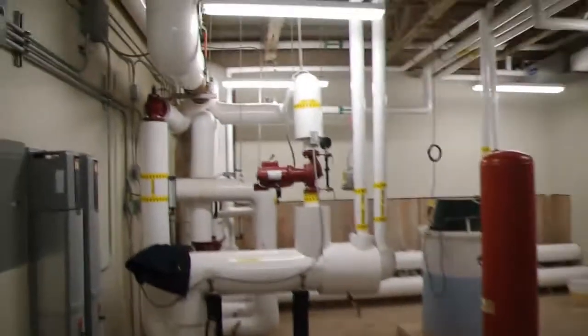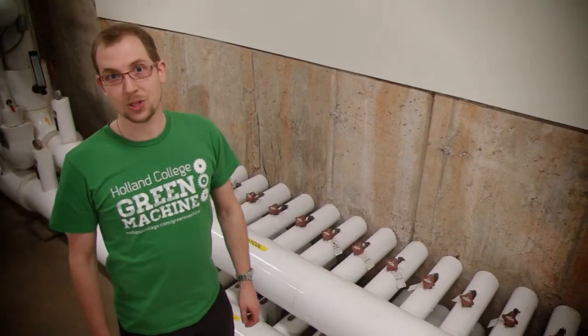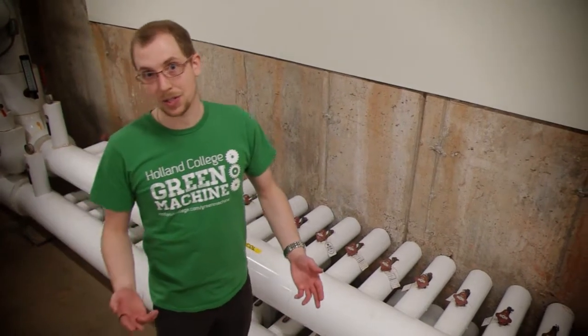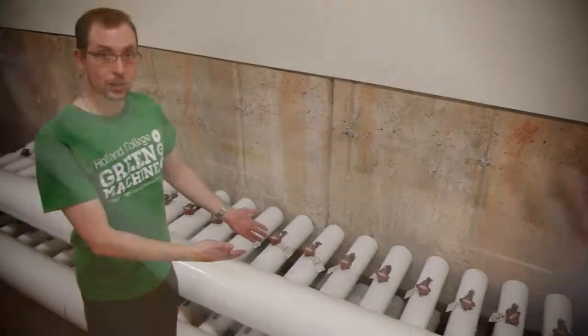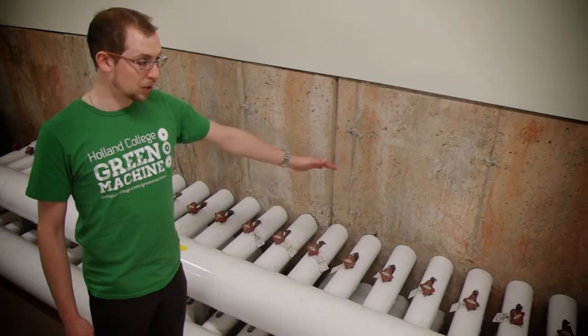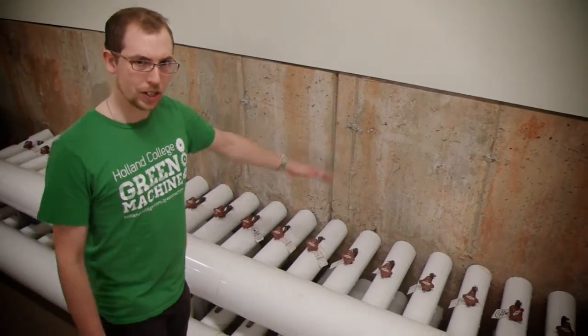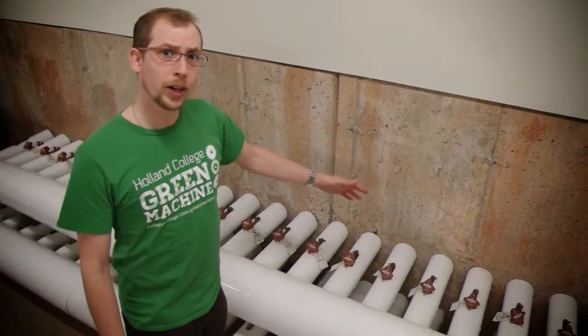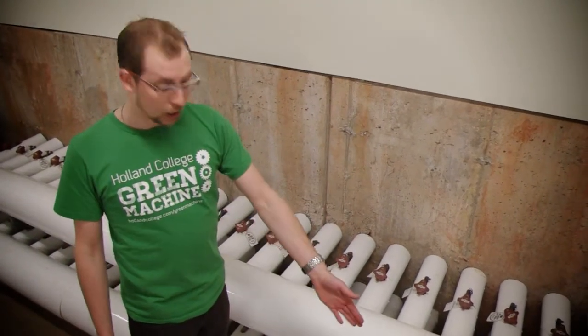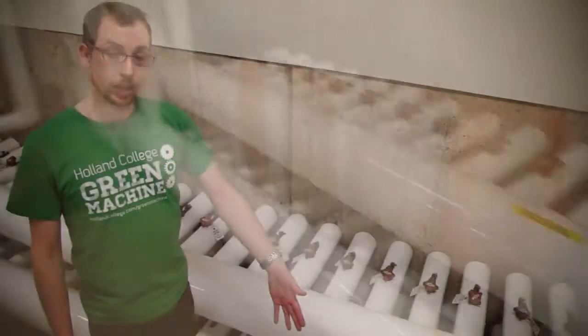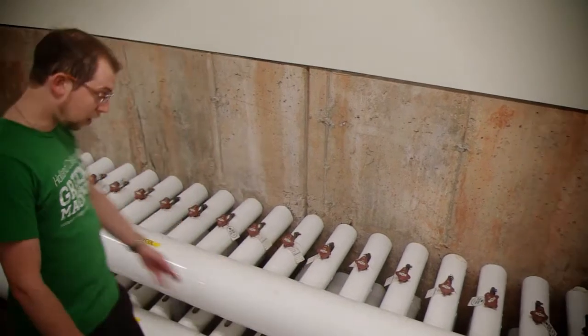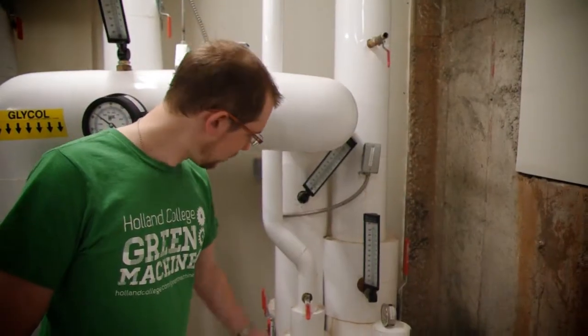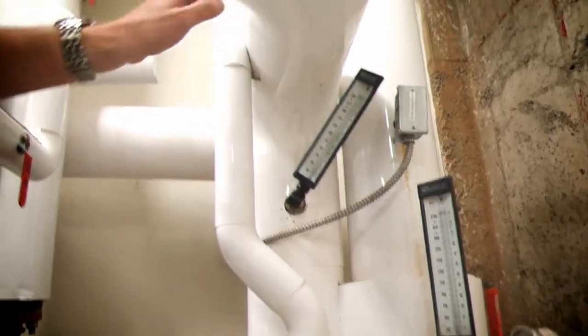The heart of the system is the building's mechanical room, and I, Dave, will guide you through its basic operations. So welcome to the mechanical room for the geothermal system, also known as the ground source heat pump. What you see right here is where the 24 boreholes shown earlier emerge into the building. This top header is what's being returned back underground, or rejected back underground. Could be heat, could be cool air, depending on which mode we're in. On the bottom here, we have the supply coming into the building. From there, it's going to fall down into here. So from there, it goes up into this pipe here where it makes this elbow joint.